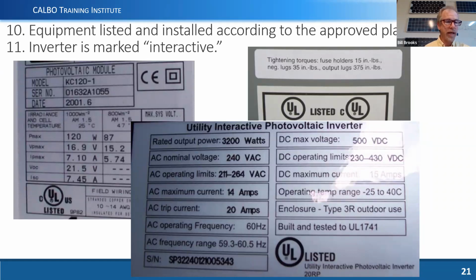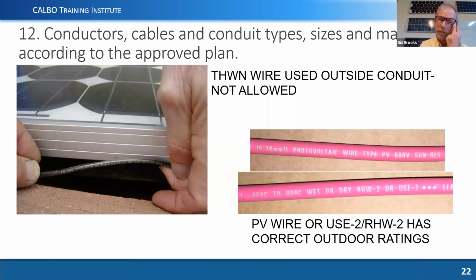But let's say we have an inverter from an older project, and maybe the customer moved away, and we bought the equipment back from the customer or whatever, to take that inverter and use it in a new installation. It would be very likely that that inverter wouldn't have all the new requirements for grid support functions for California, for Rule 21 in California, and then we're moving toward communications requirements as well. So lots going on in that area. It has to meet the requirements, has to be on these lists. Just having utility interactive on the label is helpful, but it doesn't necessarily tell you everything.